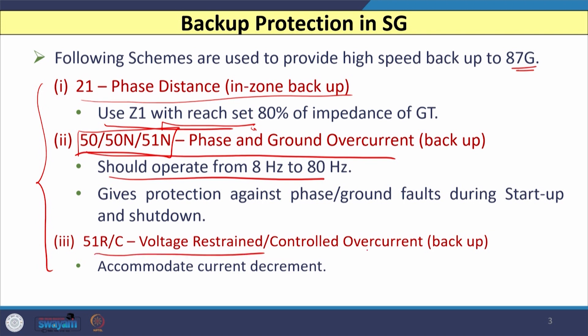The third type of backup protection is the voltage-controlled overcurrent relay, which detects the increase in fault current magnitude while simultaneously checking whether the voltage collapses. It is essentially an overcurrent relay monitored by voltage, capable of measuring the decrement in current simultaneously with the reduction in voltage. These three are the common backup protection schemes used in a synchronous generator when the conventional 87G unit fails.